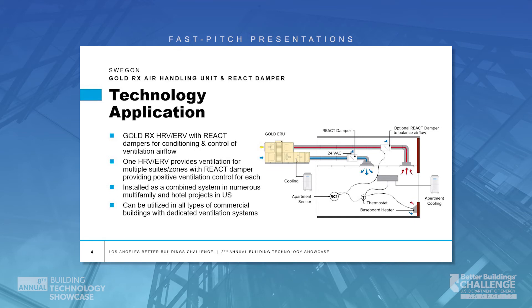The Gold RX Heat Recovery Unit and React Dampers can be utilized together to condition and control ventilation airflow into each apartment. You can utilize one large Swegon Gold Heat Recovery Unit providing ventilation air into multiple apartments, utilizing the React Airflow Control Dampers to control the airflow into each apartment. React Dampers can be utilized only in the supply duct, or for balanced ventilation, you can use React Dampers in supply and exhaust duct.